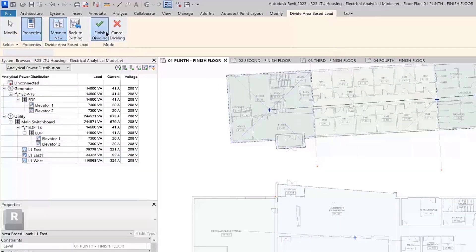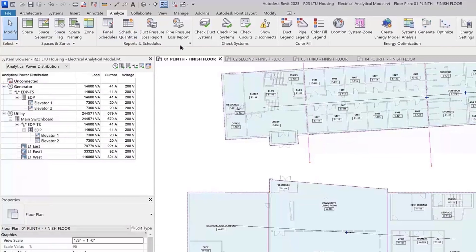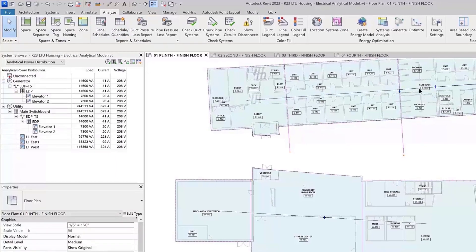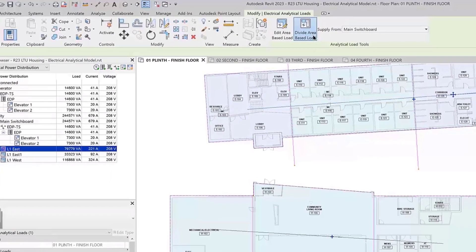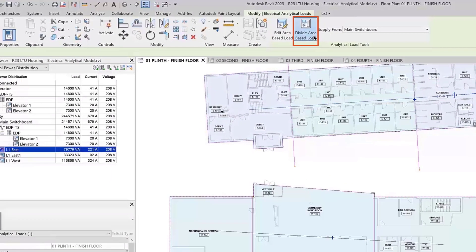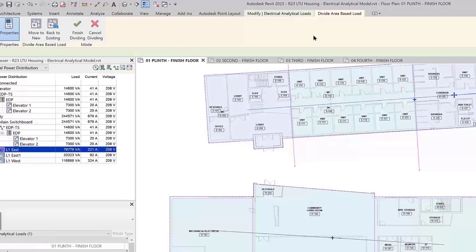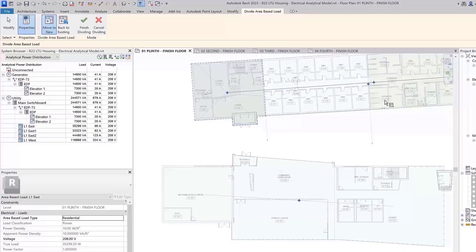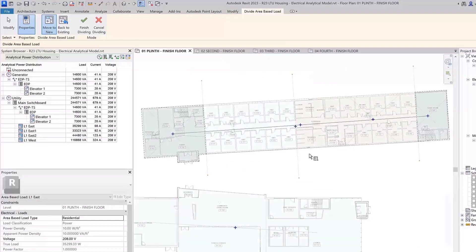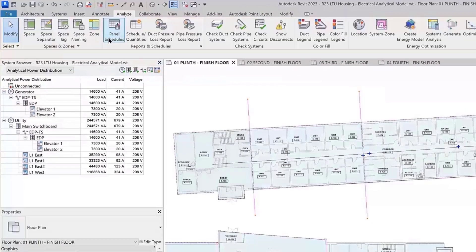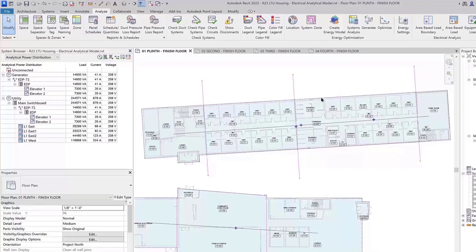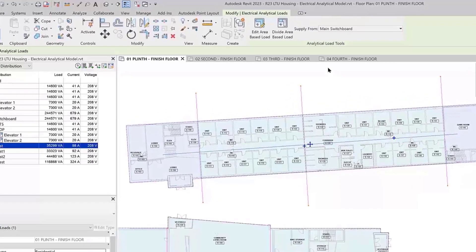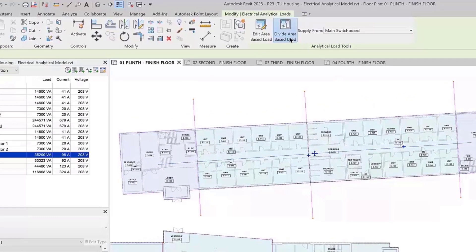However, unlike rooms and spaces in Revit, these boundary lines do not automatically subdivide area-based loads. You will need to intentionally divide the new boundaries by editing the area-based load. This provides flexibility in how you manage these loads within your Revit project, allowing you to have overlapping loads that may cover partial areas.